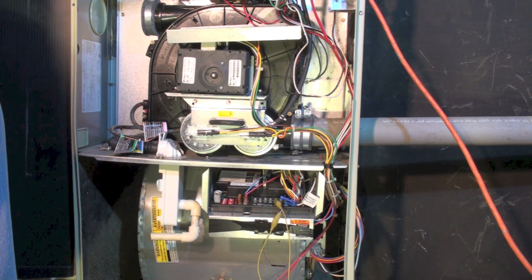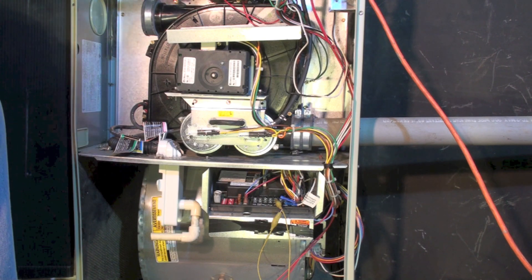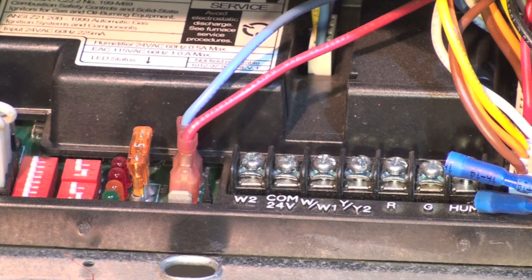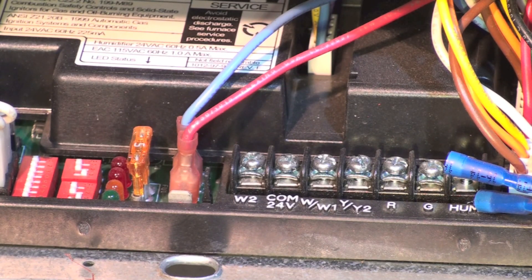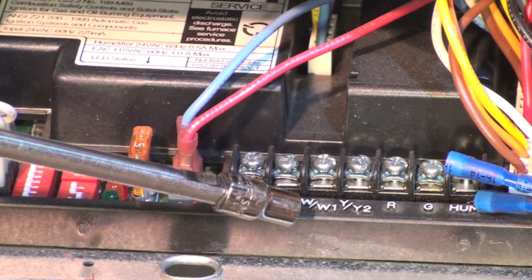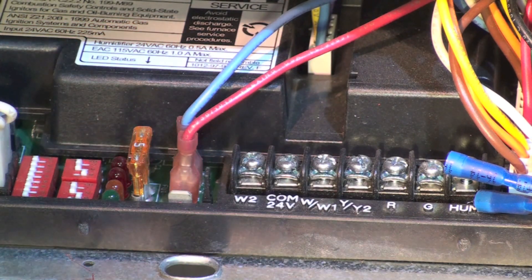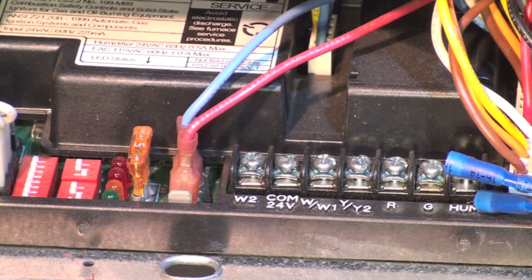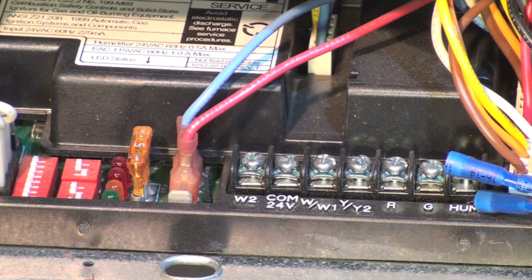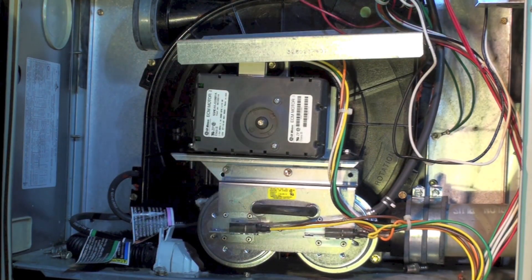Let's talk about what's going to happen when I get a call for heat. The first thing I'm going to do is give a call for first stage heat, so I'm going to put a jumper between R and W slash W1. That will bring on the inducer and start the sequence.